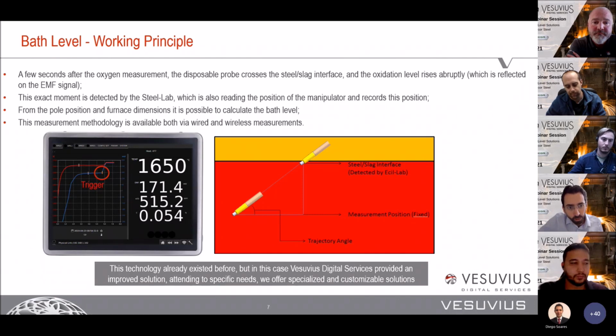When we reach stability, which we call the plateau, we take the oxygen measurement, giving us how many ppms of soluble oxygen are in the steel. We can also predict carbon and other variables. But when the probe is being retrieved and crosses the slag, the oxidation goes high - you can see on the red circle, what we call the trigger, it goes up. I'll explain exactly how it's done in the next slide, but basically we are able to detect the exact moment when the probe crosses this interface.